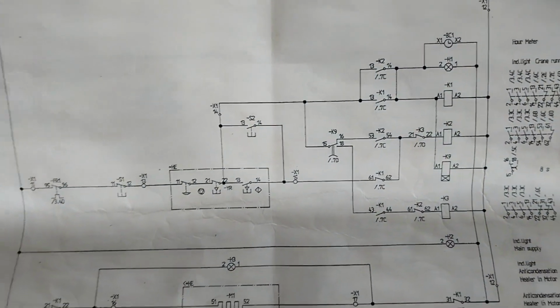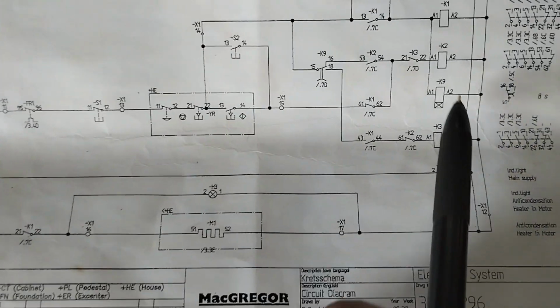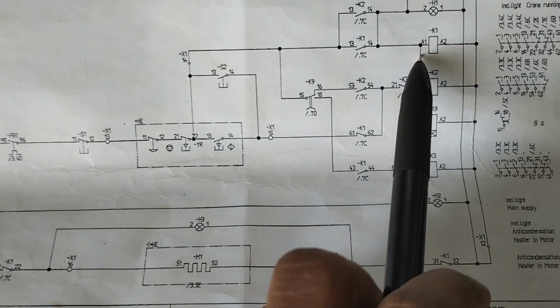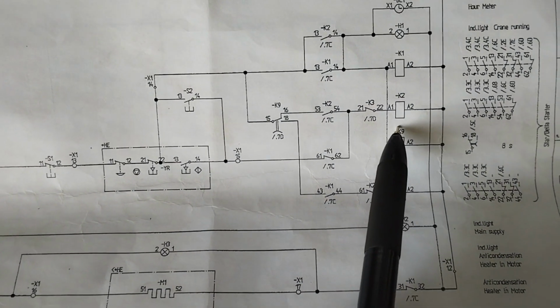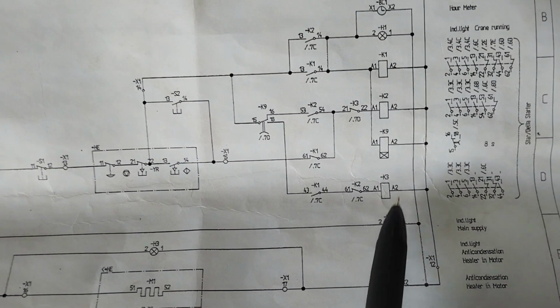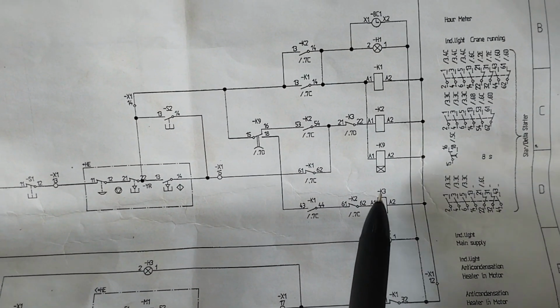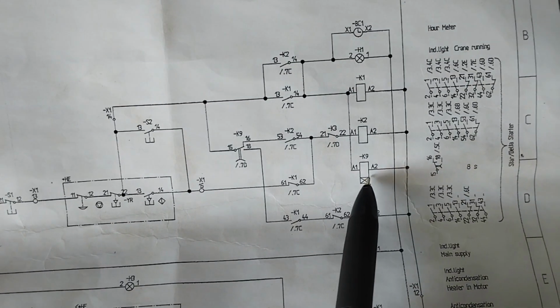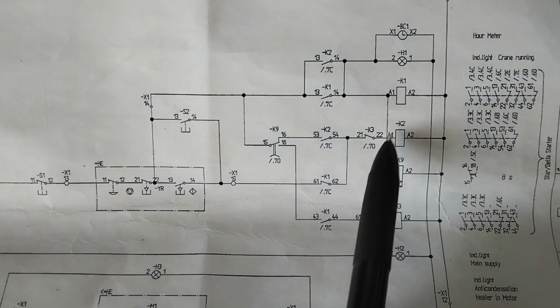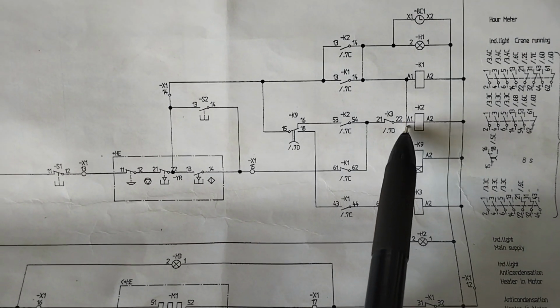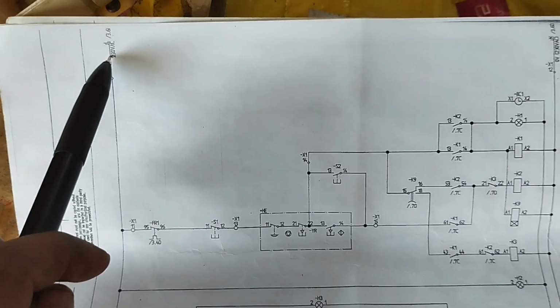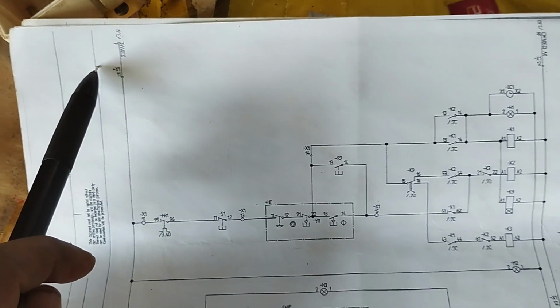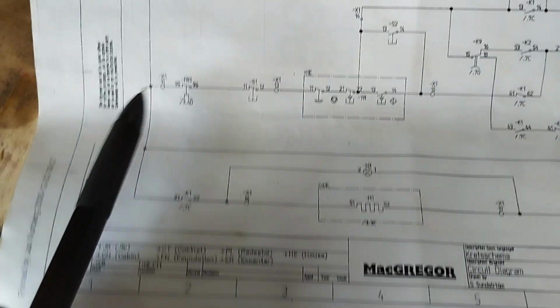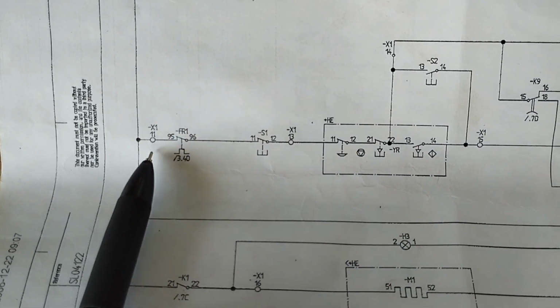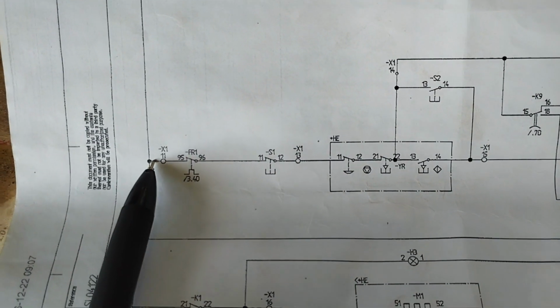This is the control circuit. Okay, as we explained in the power circuit diagram, these are the contactor coils. K1 is the main contactor, K2 is the star contactor, and K3 is the delta contactor. And K9 is the timer, that I will show you in the panel. So first of all, K2 will energize. How will K2 energize? You can see this is the power supply coming from the transformer after the circuit breaker. So we'll start from here. How the K2 will energize first.